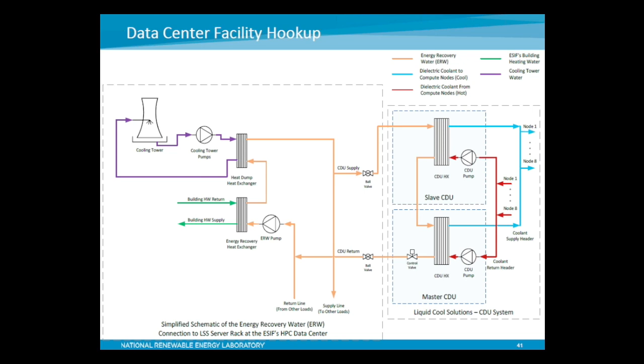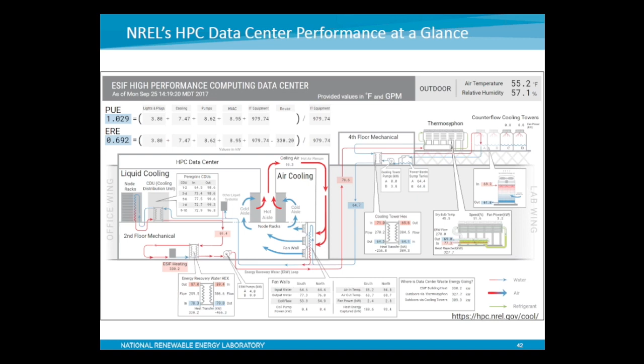But I want to bring your attention to the fact that liquid cooling is becoming much more accepted. This data center at ESIF achieves low PUEs, or power usage effectiveness, near 1, which is the limit. Furthermore, this data was just taken a couple of days ago: of the nearly 980 kilowatts of IT equipment energy being used, about 330 kilowatts is being reused and sent back to the heating system for this building. So although our demonstration system is a mere 3 kilowatts, it is actually contributing to this facility's energy reuse as we speak.